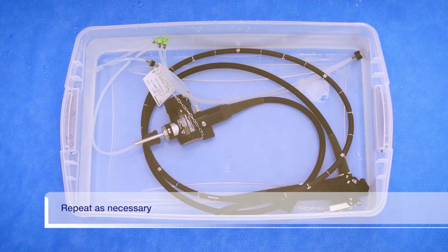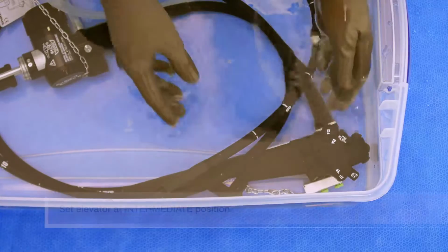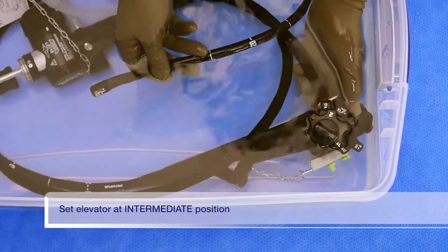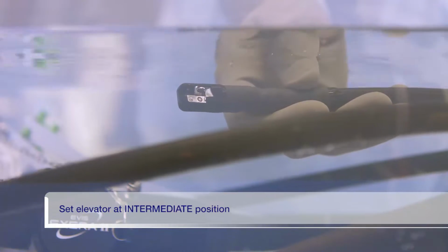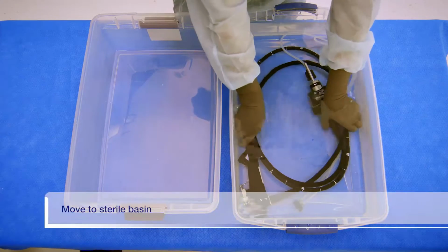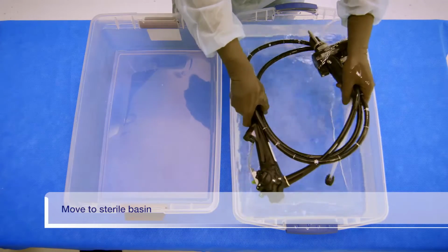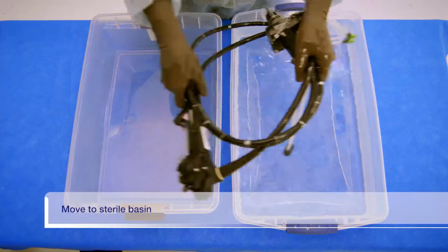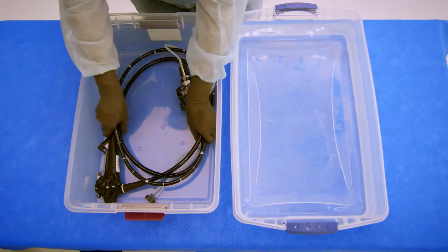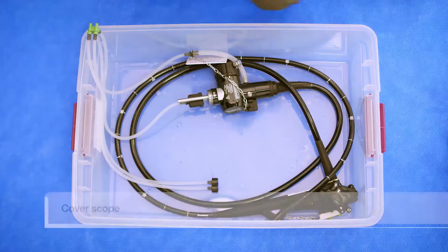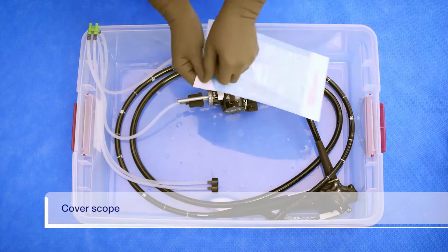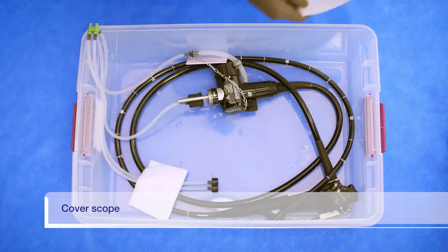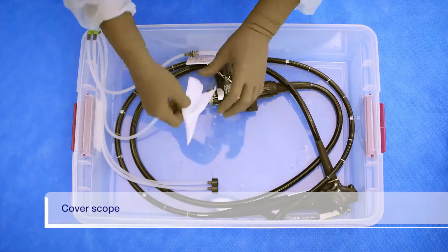Repeat the previous rinsing steps for the necessary number of times based on the rinsing method described in the disinfectant solution manual. By turning the elevator control lever, put the forceps elevator in intermediate position of the range of movement. Remove the endoscope with attached accessories from the rinse water and place them in a sterile basin. Cover the distal end and the control section of the endoscope with sterile, lint-free cloths to prevent splashing from the channel openings.